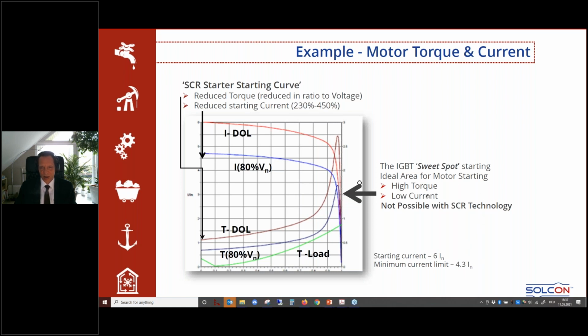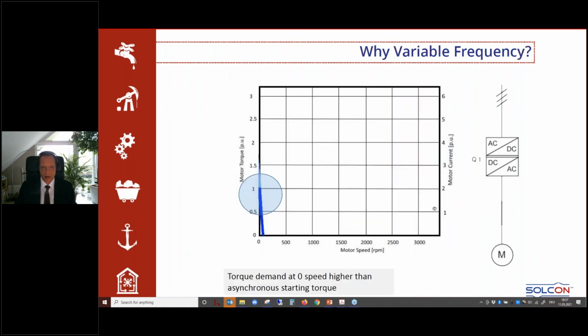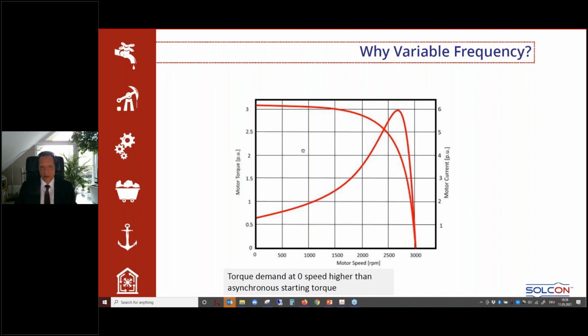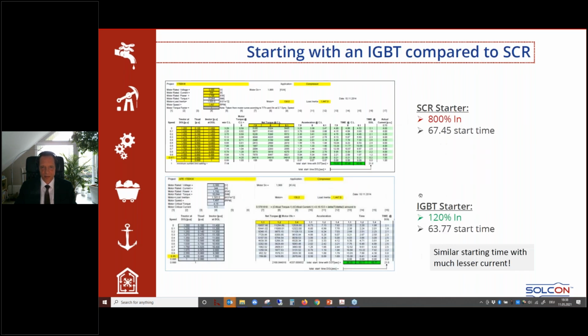If we have high torque and low current, this is not possible with the SCR, with the classic soft starter technology. Also, a question: why choose variable frequency? If you have torque demands at zero speed, where the torque is higher than the asynchronous starting torque, you see here the starting torque in this case is 0.7. You had a torque demand of over one. This is not possible with a classic soft starter. In this case, you need to apply IGBT and frequency starting.